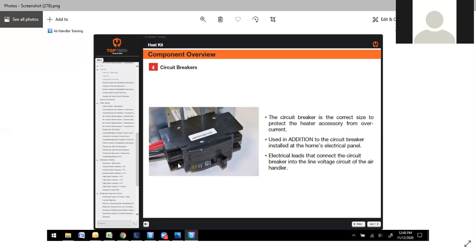Do be sure that the connections on the factory side are secure and tight, as well as when you're installing your line side. Make sure they are good and they are tight. If not, they will create heat eventually and actually cause this breaker to trip. It'll trip more than likely a few times, but you can actually cause that breaker to melt.